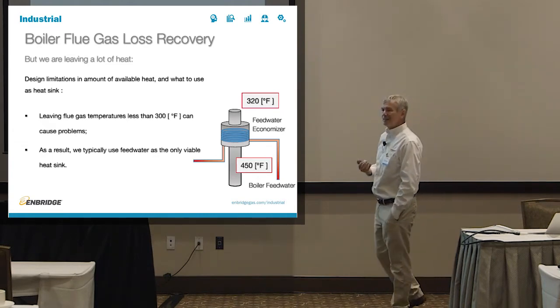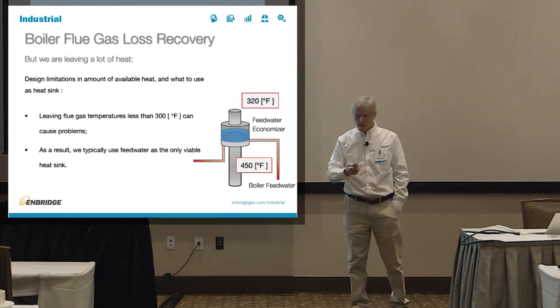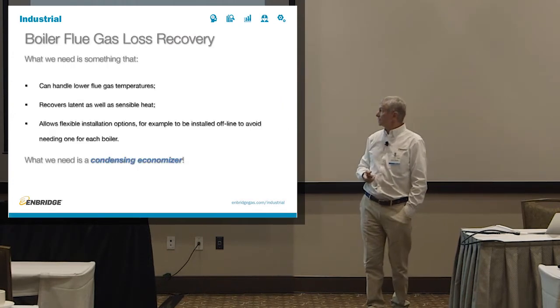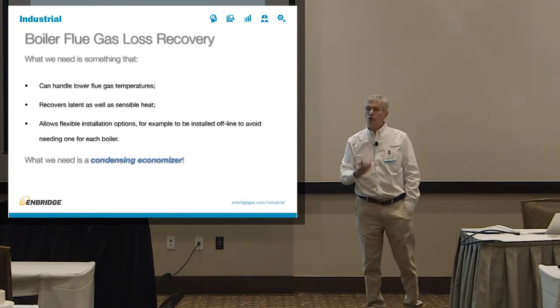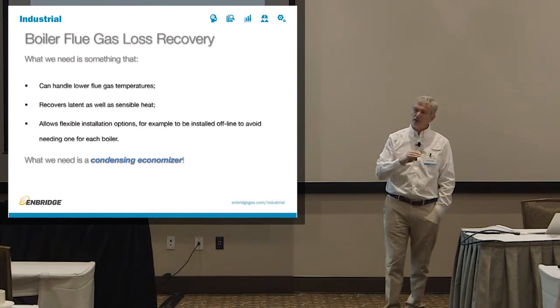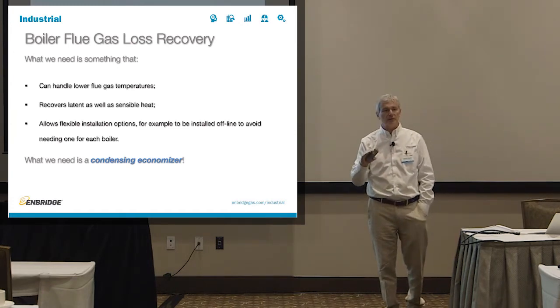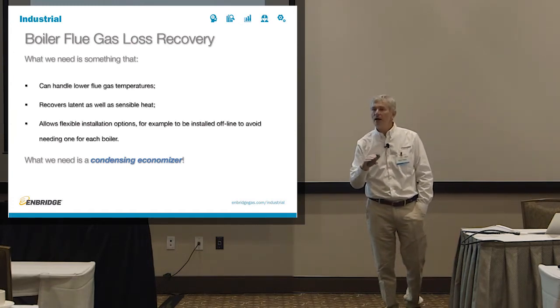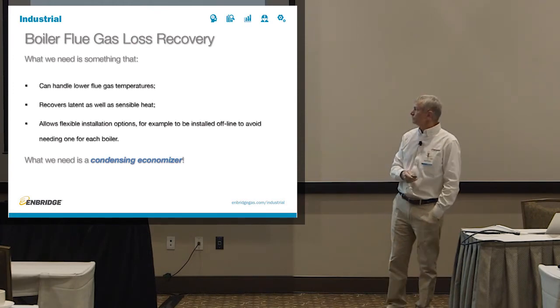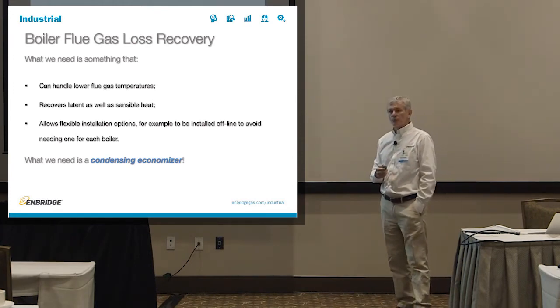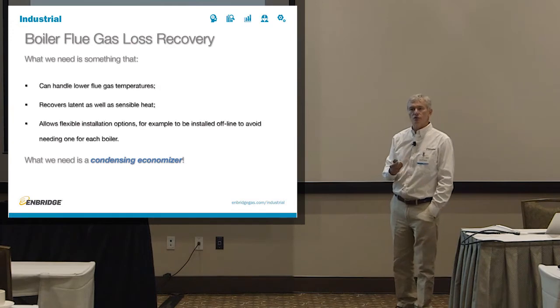So what we really need, when you look at a feed water economizer, is something that can handle lower flue gas temperatures. Instead of exhausting at 320 degrees F, wouldn't it be nice if we can exhaust at about 100 degrees F? It would be good to recover some of the latent heat, not just sensible heat.